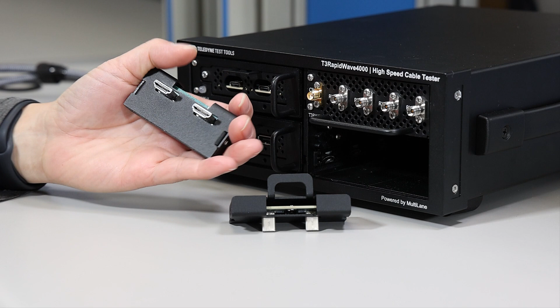The adapter should be checked periodically with a calibration module to determine if it is worn and needs to be replaced. This is easy and fast to do. Simply insert the calibration adapter into the production adapter and run the module calibration routine in the application software.